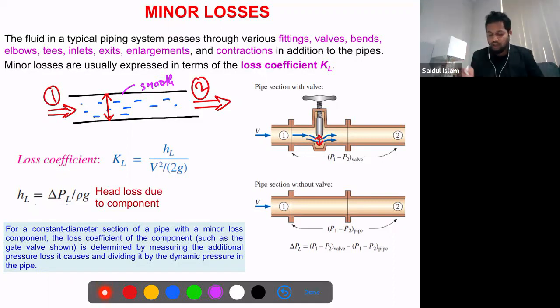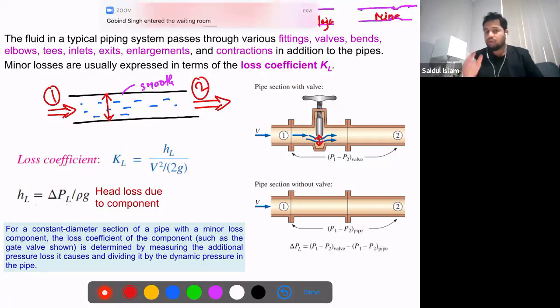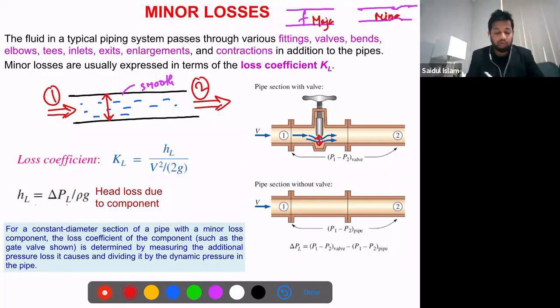my conclusion is, now I will show you two things. We have one pipe where we have the friction loss. And this is one pipe. Let's say we have a stenosis section like this. So for this pipe, we have the major loss. Here we have minor loss. So I'm talking about when we have all these things, that means fittings, valves, or any of this arrangement or inserts, this minor loss, in some cases, could be more significant than the major loss.